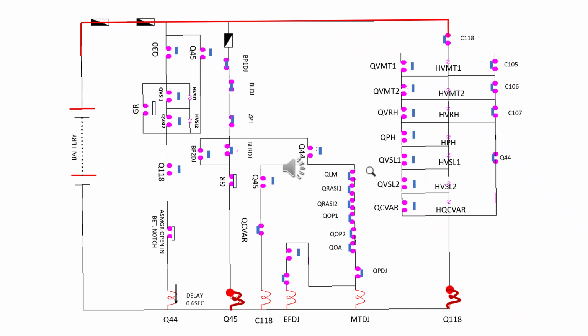it should not be in the mid of the notch. Suppose your notch positions are 1, 2, 3, 4; it should be in a full notch, not in a mid notch between 1 and 2 or 2 and 3. At that time it will be in closed condition, so your Q44 will be energized. After energizing Q45, your Q44 will be energized. So you have seen that Q44 is energized after Q45 energization and Q118 energization.